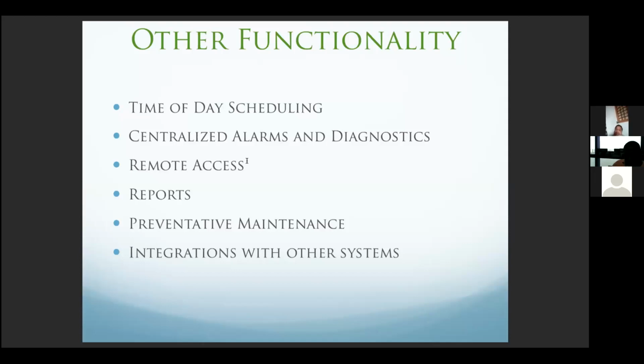Preventative maintenance. So sometimes, depending on the system, you may be able to schedule, let me know after X amount of time to change the filters, stuff like that. Also, it may be able to tell you when to fix your equipment. It's time or it's not time yet. You may also be able to look at things like filter status, for example, which is basically just determining the pressure before and after the filter to see if it is clogged or not. And that gives a signal to the controller to let it know.